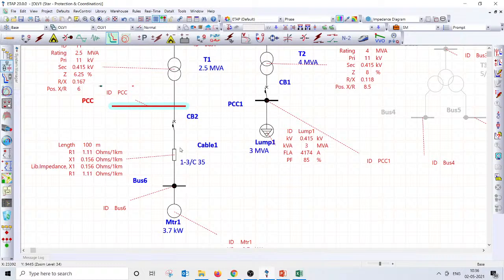Instead, if you place this 3.7 kilowatt motor not in the PCC, but probably somewhere downstream in the MCCs, there is always an advantage: the short circuit current of an MCC is much lesser than that of the PCC. You may have 50 or 65 kiloamps in the PCC, whereas in the MCC the short circuit current is less.